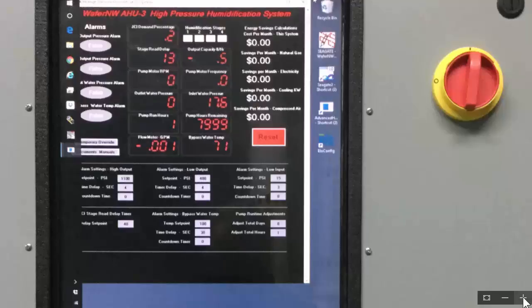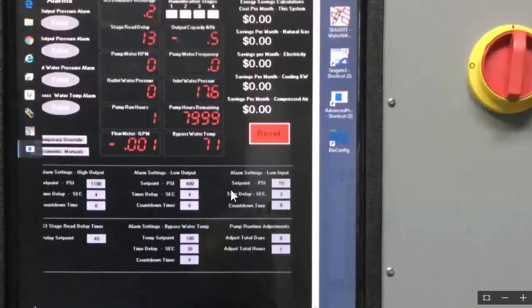Now when I talked about input water pressures, which was this guy over here, we talked about the time delay in seconds. What is going on there is that once you get to this alarm threshold, it doesn't shut off right away. It's kind of a proving mechanism that says, hey, are we really in this condition, or are we in this condition just for a short period of time, or a split second type scenario? So this is a proving 4-second condition that yes, we've gone into 1100 psi for 4 seconds, and then we shut the system down. And in order to restart it, you have to push this reset button here, or the one below on the panel itself.